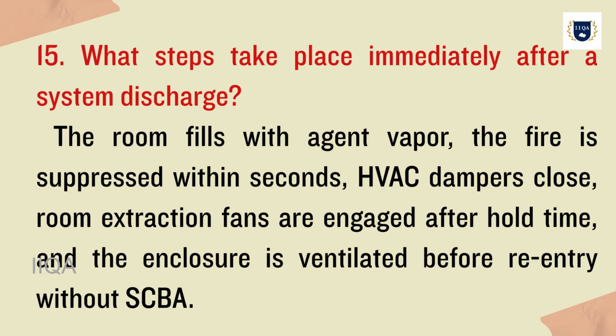15. What steps take place immediately after a system discharge? The room fills with agent vapor. The fire is suppressed within seconds. HVAC dampers close. Room extraction fans are engaged after hold time, and the enclosure is ventilated before re-entry without SCBA.